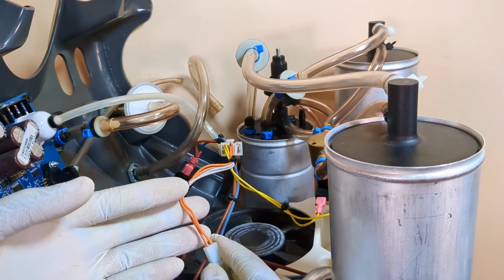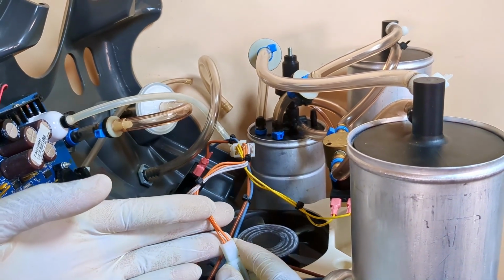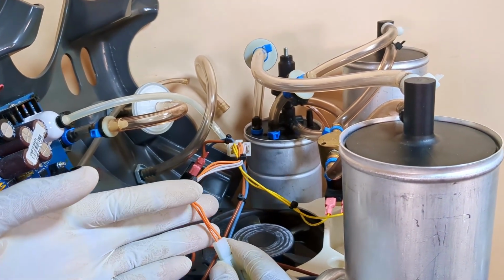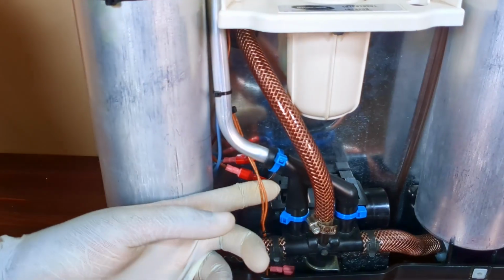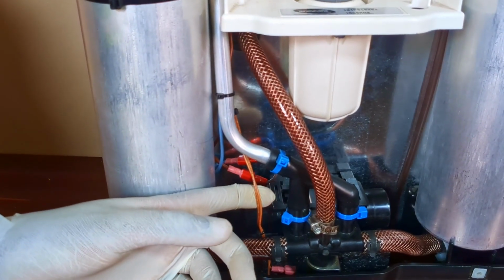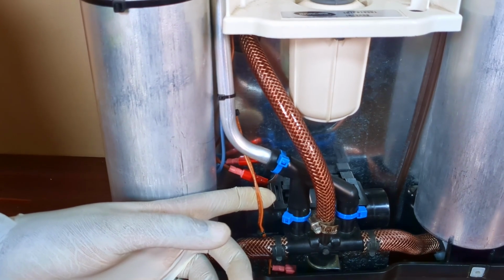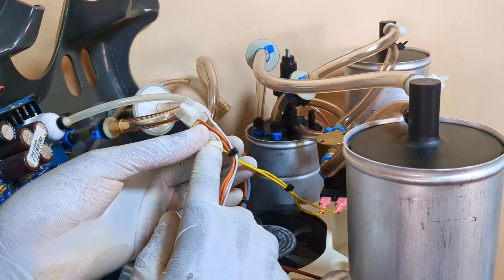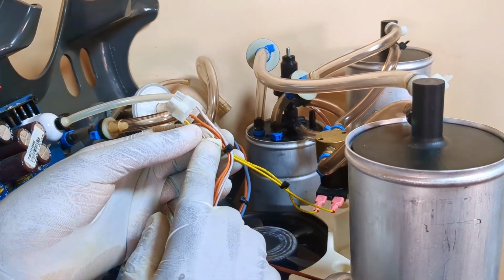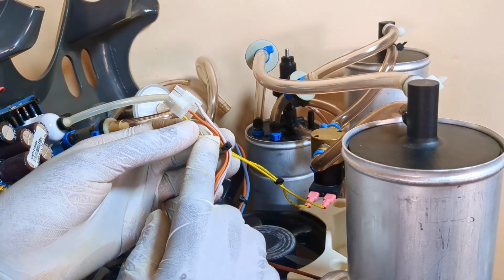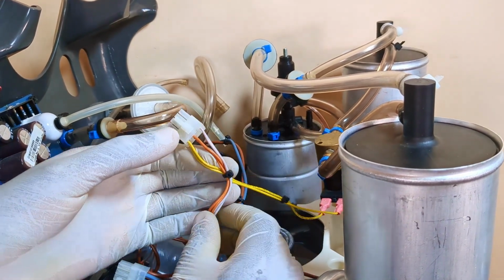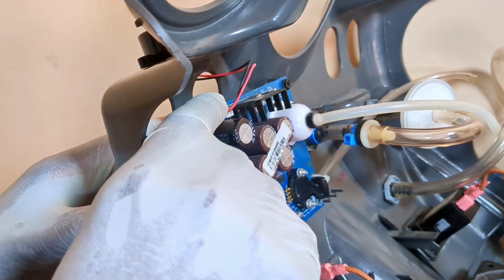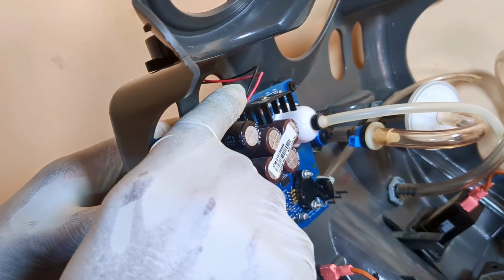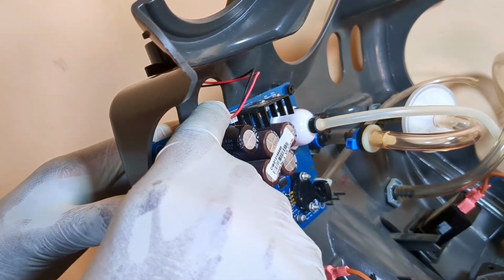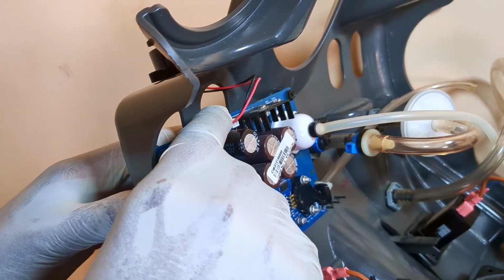These orange cables from the board power the 4-way solenoid valve with 24 volts DC. These are the cables that bring power to the pilot operated 4-way solenoid valve. The yellow cables power the pressure equalization valve with 24 volts DC. These black and red cables power the buzzer with 12 volts DC.